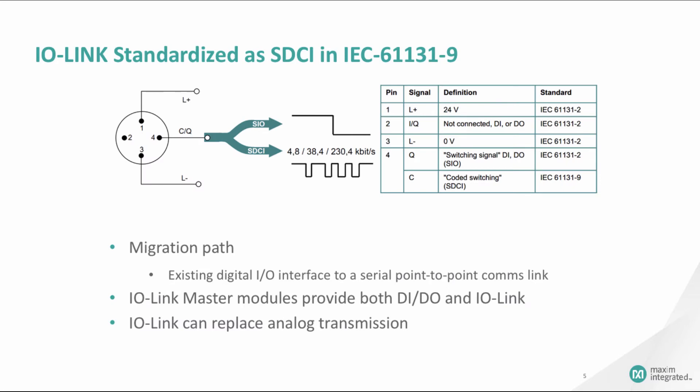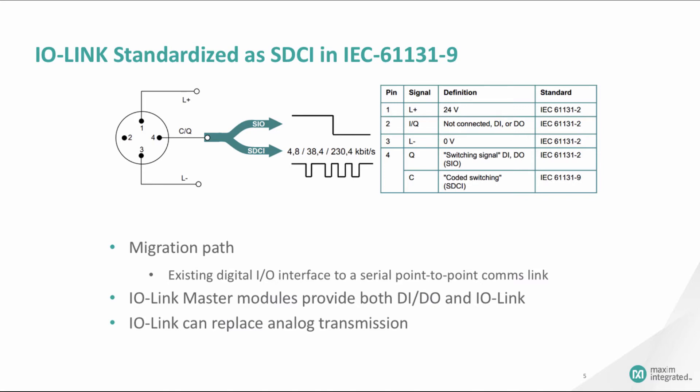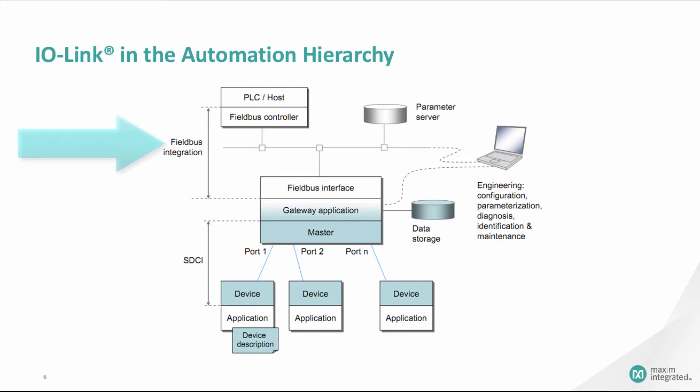The next step in sensor evolution is the IO-Link standard. IO-Link is officially known as the Single-drop Digital Communication Interface, or SDCI. The IO-Link standard is IEC 61131-9. IO-Link sensors keep all of the best that binary sensors have to offer and add a bidirectional data line — the sensor can now send and receive information to or from the master. IO-Link masters provide both binary sensor and IO-Link communication, allowing IO-Link to be added to an existing system easily. When combined with gateway capabilities, this system can become a field bus IO node.